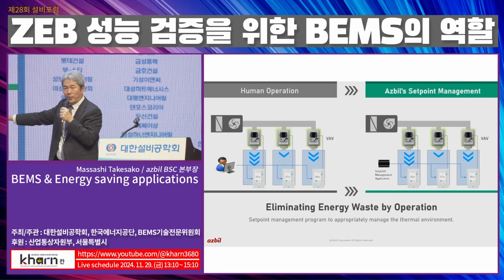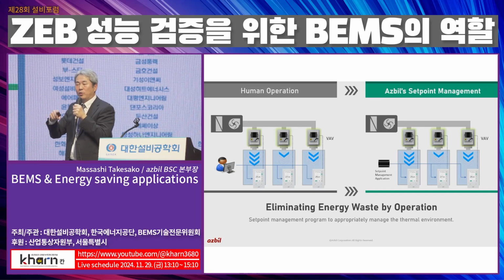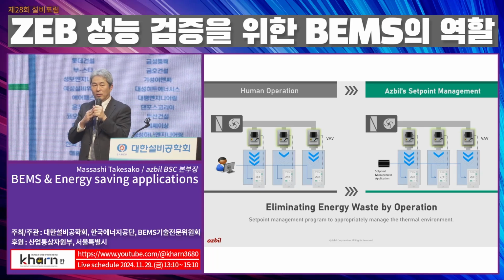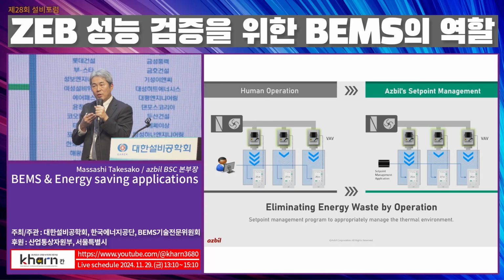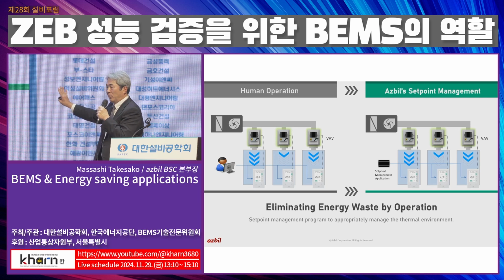When the AHU stops, the set point will go back to the original, which is 24 degrees, every day. That is also one of the very important points to minimize energy wastage. Of course, we have various kinds of set point management systems. As I said, this one changes the set point back to the original once a day, but in some applications, for example, one hour later the temperature set point gradually goes back to the original. This is also one way to avoid energy wastage. Anyway, this is the application.